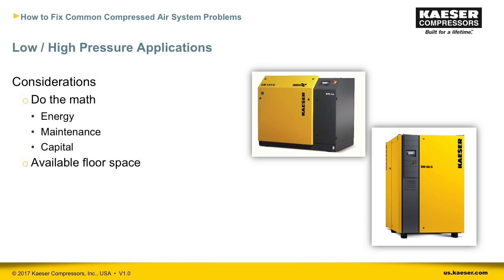When considering adding in different types of equipment, you'll want to do the math and consider the return of investment. If, for example, you only have a few air knives, it may not pay to install a separate blower system, but it will definitely pay to buy engineered air nozzles designed for the task rather than homemade solutions. In your calculations, be sure to consider energy and maintenance savings, capital costs for the equipment, and available floor space. Your best bet may be to work with a compressed air specialist who can run the numbers for you and develop a plan that would best fit your budget, application, and plant layout.